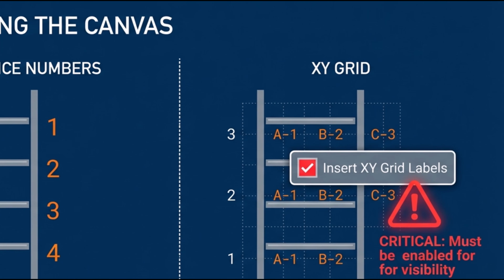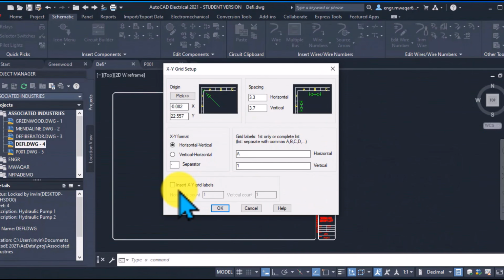You know, the analogy that immediately came to mind when I was reading this section was the board game Battleship. That is actually the perfect analogy. It works exactly like Battleship. You define zones on the paper. You might have numbers 1 through 9 running horizontally across the top of the page. That's your x-axis. Right. And then you have letters A through F running vertically down the side. That's your y-axis. So under this system, the component isn't located on line 10. It doesn't care about rungs. It's located in zone B4.